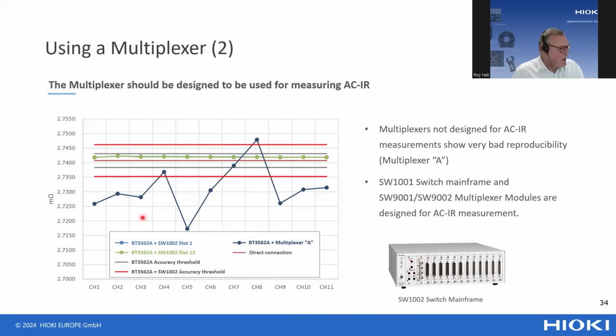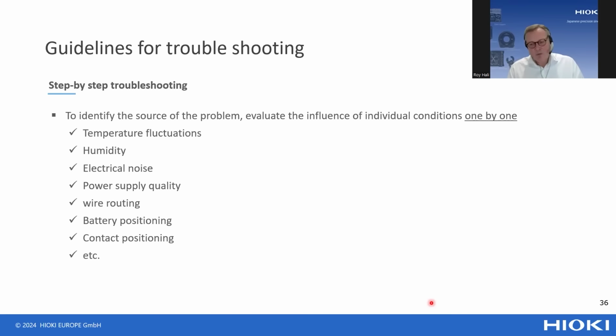Change only one of the possible causes, like, for instance, the routing of the measurement wires, and check if that gives an improvement. If that isn't the case, then maybe fix another of the items, like, for instance, is there any metal plate nearby the wiring? Remove the metal plate and see if that has an impact, an improvement on the repeatability of your measurement. This you can do for many of the causes that are possibly the reason for a bad reproducibility. So the general rule is change one thing, do a test, and then do another test when you have done another change. So step by step, we'll identify the reason why you have inconsistent measurements.